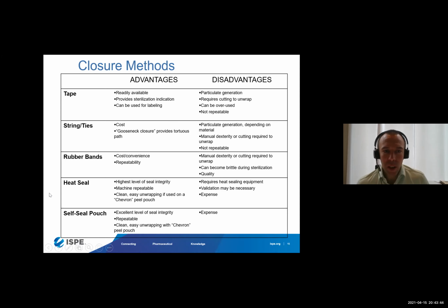Down here at the bottom, the heat seal or the self-seal, typically these are closure methods when we have an integrated pouch, the combination Tyvek and film compared to the paper and film pouch. So these are either closed with a separate tool, equipment called a heat sealer, or some of these pouches have what we call a self-seal option, where the adhesive is directly integrated on the pouch. So of course, there are advantages and disadvantages to these different options for the pouch closure. The heat sealer is nice because it is a separate piece of equipment. It has operating parameters that can be locked down as part of the validation. This is the highest level of seal integrity, repeatable, very clean, easy. However, it is another piece of equipment to maintain. Validation is necessary, might be an added expense.